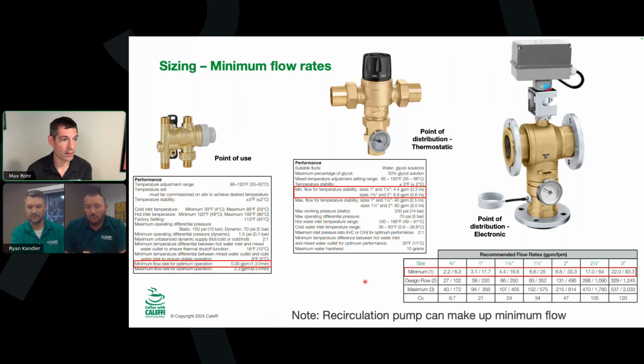Yeah, that's a good troubleshooting tip just for anything: write down some of the other details, like what time is it? Is it 4 in the morning that you're noticing this? Are you having issues in the hotel only when you're at full occupancy, when it does not keep up? That could be a completely different thing. That could be that the thermostatic mixing valve has scaled in a way that it can't get as much hot water out to the building as it should, or it could be undersized, which is a pretty rare one, I would say. But those are good things to know. Like what is the demand right now? Is this like at the minimum or maximum of what you would expect? And without even having engineered the building, that can be useful for troubleshooting there.